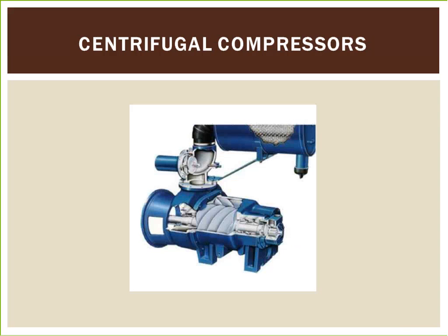The centrifugal air compressor is a dynamic compressor which depends on transfer of energy from a rotating impeller to the air. Centrifugal compressors produce high-pressure discharge by converting angular momentum imparted by the rotating impeller. In order to do this efficiently, centrifugal compressors rotate at higher speeds than the other types of compressors.